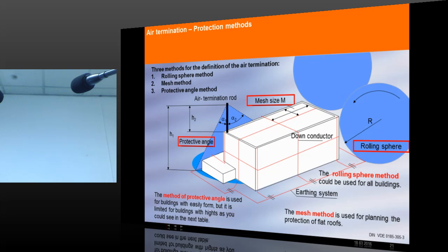The second protection method is the lightning air termination mesh. In simple terms, you can have a rod on top of the building which offers an angle of protection. If you have a large building, you need several rods. The second way is to have a mesh at the top of the building, which is one of the easiest ways. And the third way of protection, which is not explained in the standard, is to have a catenary wire. In large substations to protect the transformer, or sometimes in oil installations, refineries, petroleum storage installations, to protect a tank, two structures are erected and a catenary wire is connected at the top, which will give a certain angle of protection.